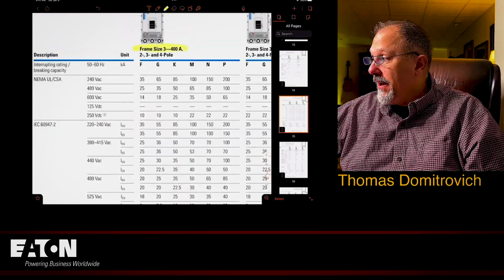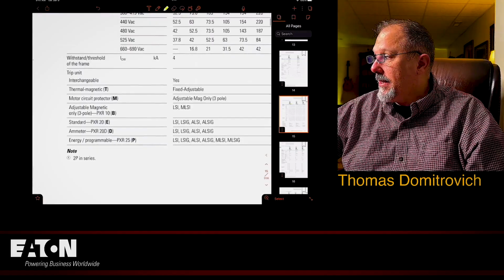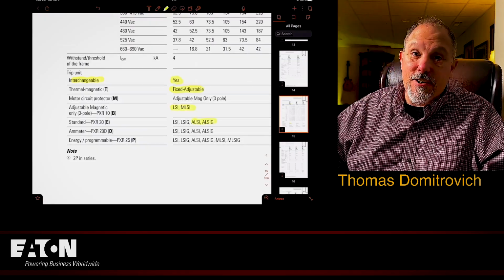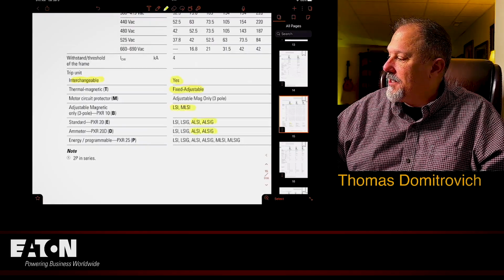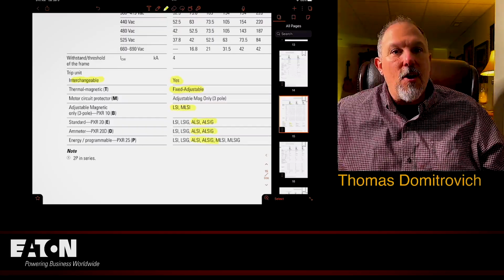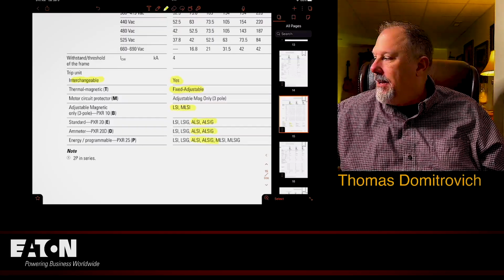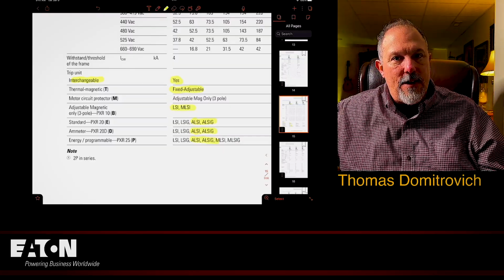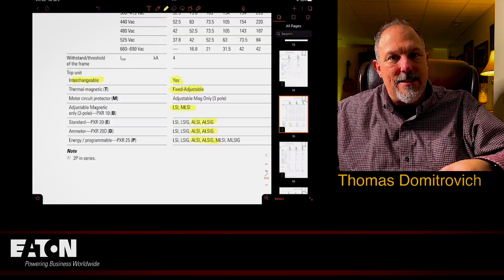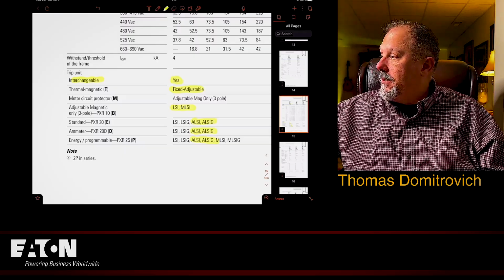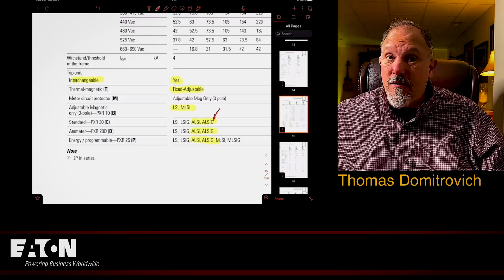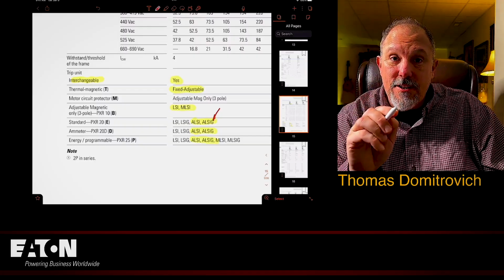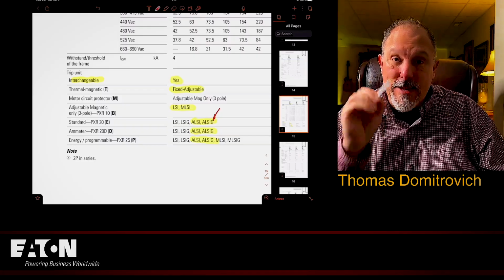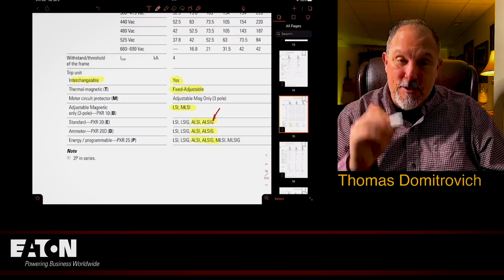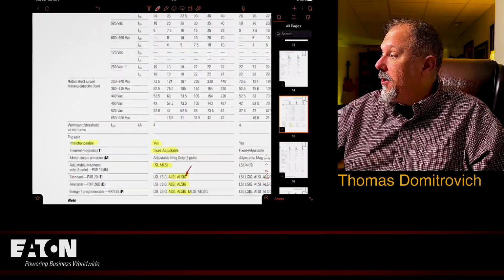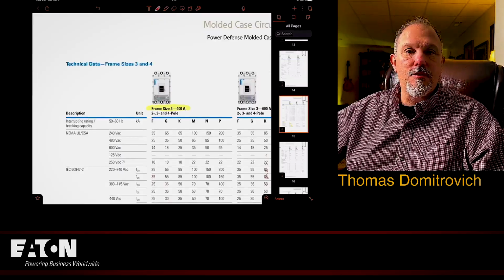breaker. So frame size 3, look at this and look at, there's the magic right there. There's the magic. Oh gosh, I love it. Look at that. Arc flash reduction maintenance switch. ALSI, arc flash reduction maintenance switch, long time, short time, instantaneous. And if you throw the G in, throw that G in there, that's ground fault protection of equipment. And we'll do another session, short session, on when should you specify a ground fault protection of equipment. So there we go. I would say we found the answer to our questions.